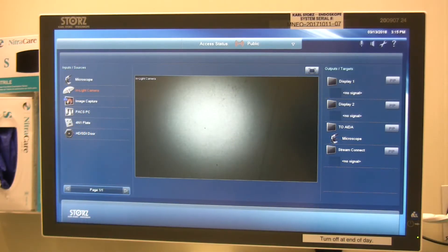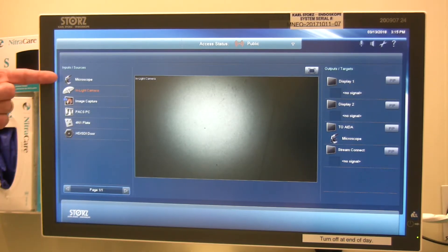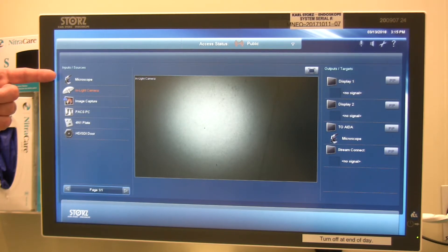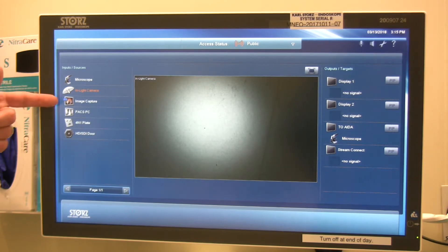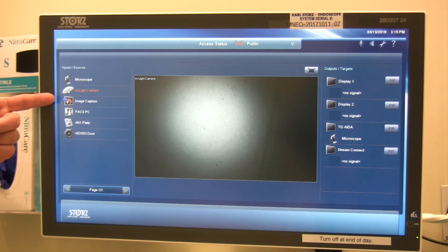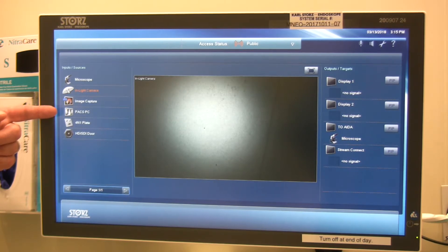Now we're going to talk more specifically about the video inputs along the left side of the screen. On the top, we have the microscope — in this room it's plugged into an HD-SDI wall plate and always connected, so we've labeled it microscope. Video source number two is the in-light camera, the camera in the surgical light. Input source number three is image capture, giving you a preview of what you're seeing on the AIDA at the touch panel. The fourth video source is the PACS PC, so we can take a source from the PC and send it to any one of the displays.